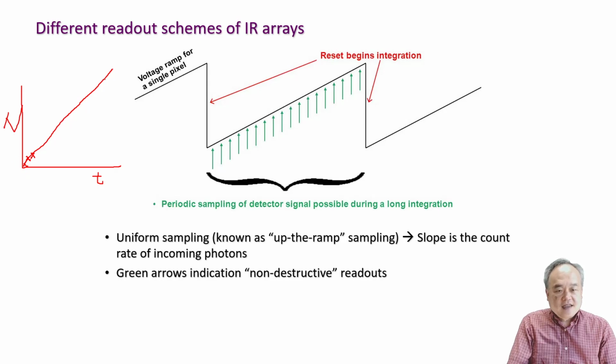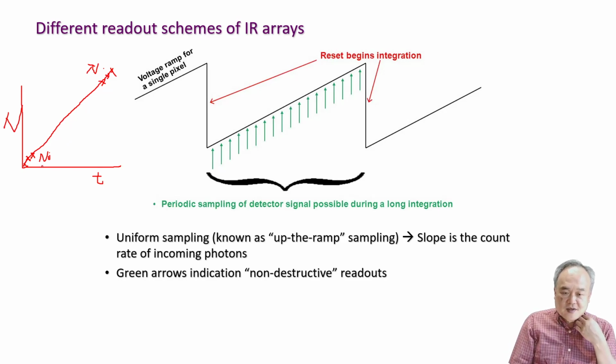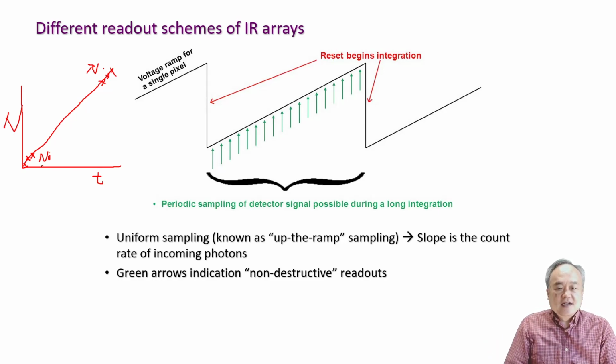Then take another 3 measurements near the end, median combine these 3, and you get the final. Instead of a single measurement at the beginning and at the end, you make a certain number of measurements at each. It is statistically more sound, and the noise is smoothed out and canceled out, so that you have a nice robust measurement.